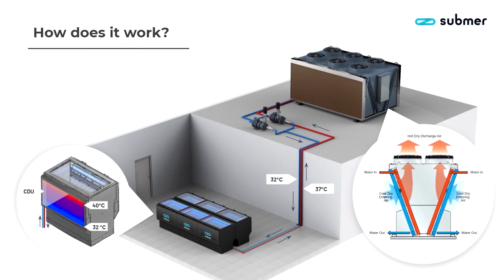If the outdoor coolers, evaporative coolers, or chillers are replaced with dry coolers, that's where we gain the biggest efficiency. You can see from this slide that the temperature range at which we operate, a very conservative range, allows us to run dry cooling infrastructure anywhere on the globe without having to chill the water.